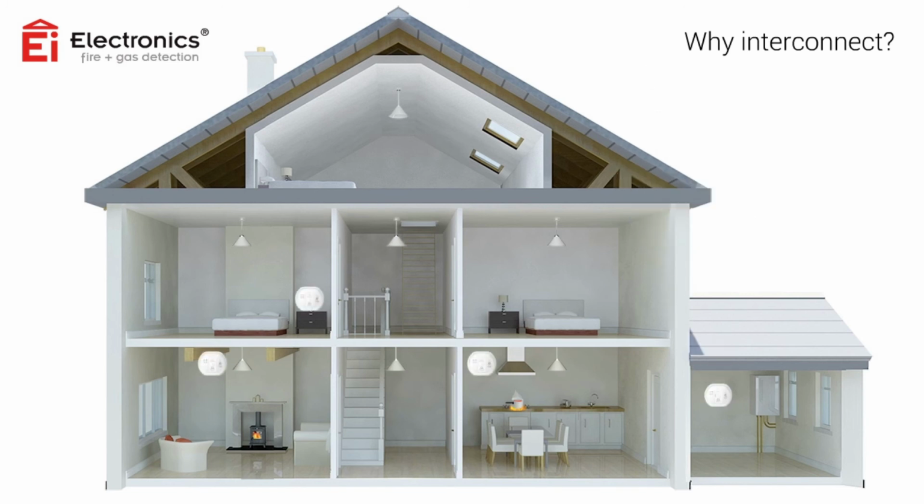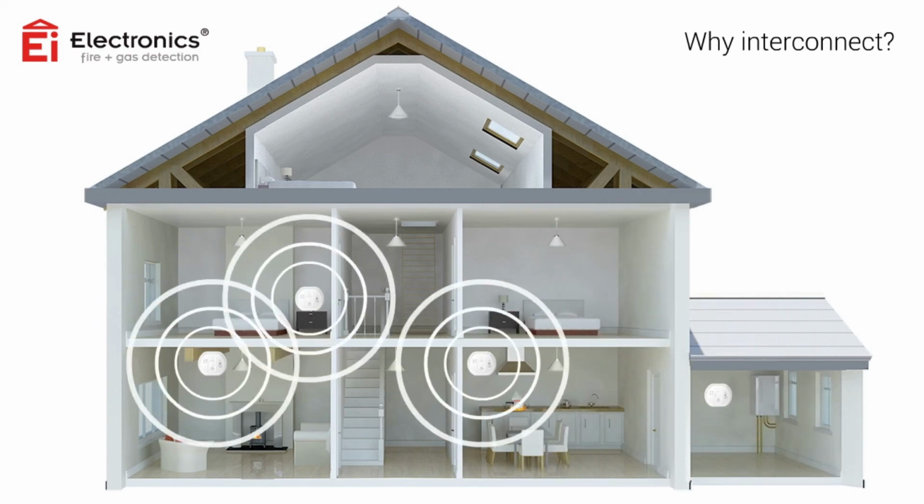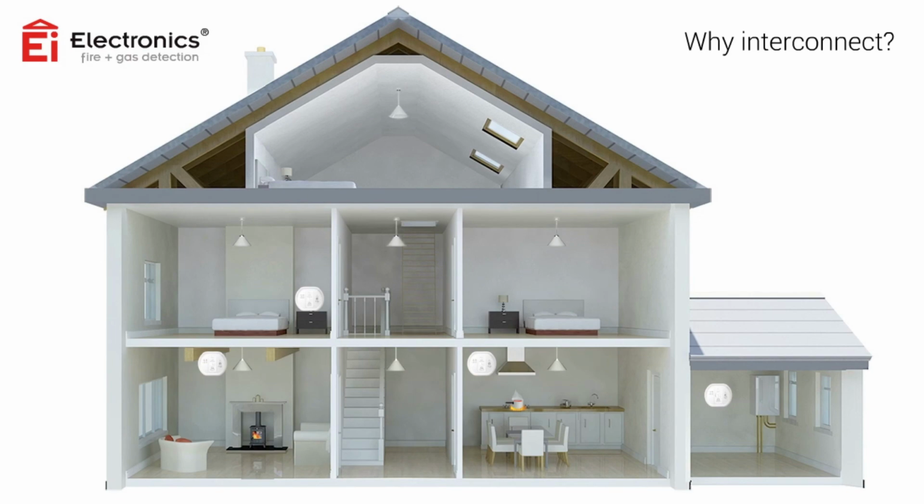The advantages of interconnecting are: A. An alarm is still placed close to the potential source, which should facilitate early detection, and B. The alarm located in the occupied area does not have to wait until it detects carbon monoxide to sound, therefore providing early warning.